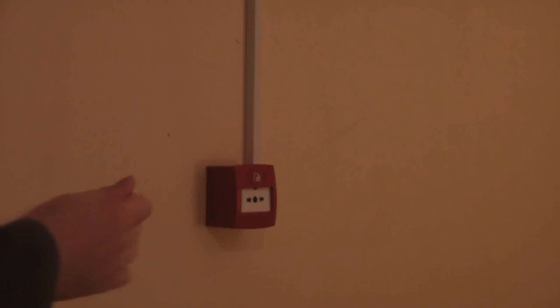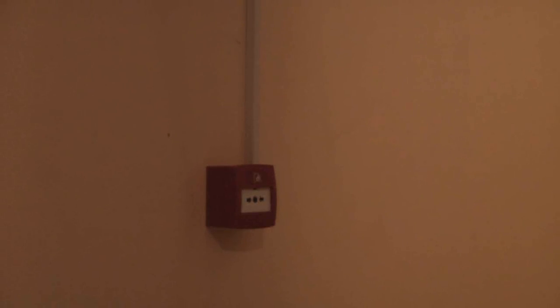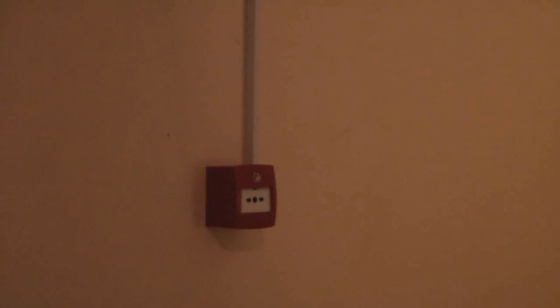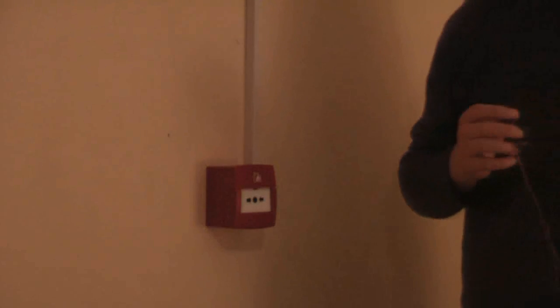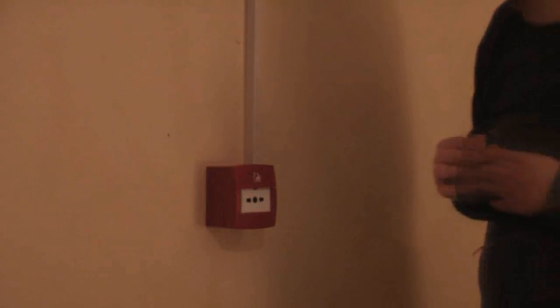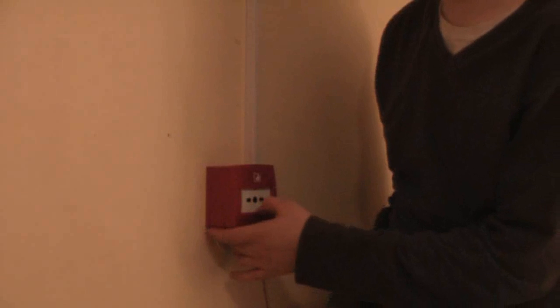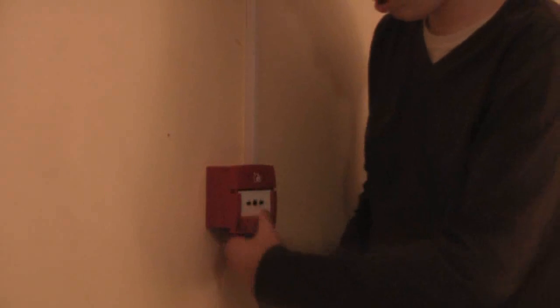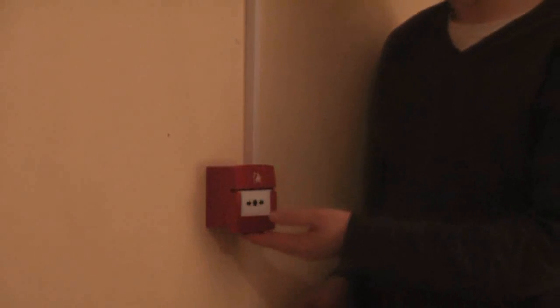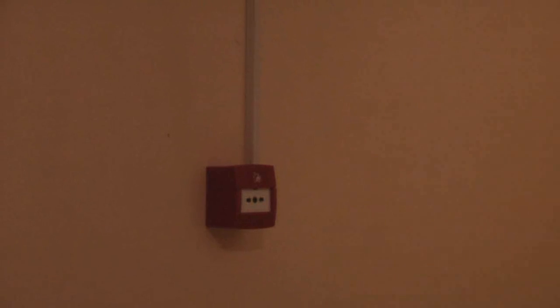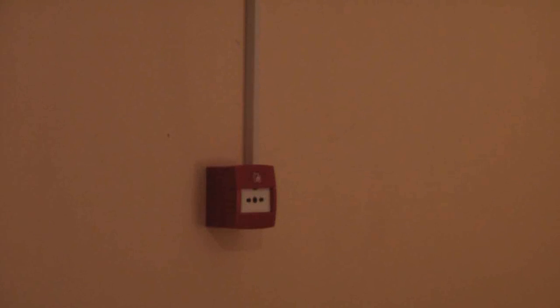Sorry about that. The detector has just come off again on the ceiling. Sometimes I have to blow air through to clear the optical smoke detector. I am not going to bother you through the video because it is just going to take too much effort, and it shouldn't happen again by the way. So I am now going to set it off by the call point. Now we are going to reset the system, push it up, turn it off by the plug and turn it back on. I do apologize for it going off again, but at least you know the optical smoke detector works.